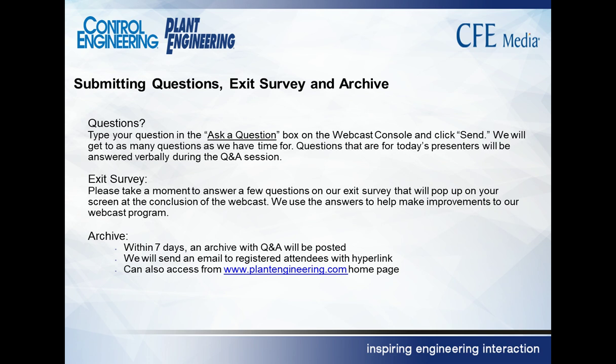The first question, Gene, is, in a large pumping station application, how does control using valves compare to control using speed? Specifically, the response to demands, surges, and other system changes. That's a good question, Kevin. Thank you for that. That's always a concern. You don't want to make a change that's going to make it more difficult to control your system. In fact, variable speed drives will produce a very quick response and a very controllable response to inputs from whatever operational controls are coming in.